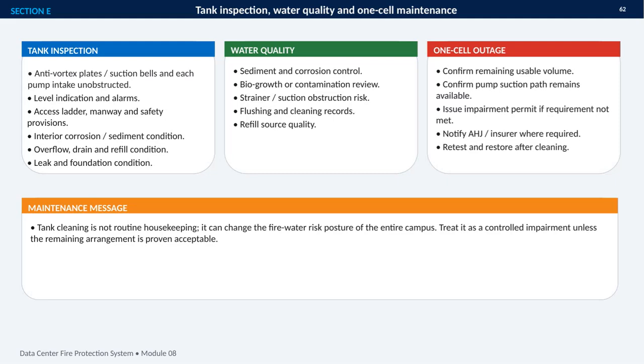This section focuses on tank inspection, water quality, and the controls required when one tank cell is taken out of service. During inspection, I want to verify that anti-vortex plates, suction bells, and every pump intake are unobstructed. We also check level indication and alarms, access and safety provisions, interior corrosion or sediment, overflow, drain and refill functions, and any signs of leakage or foundation damage. Water quality is equally important. Sediment, corrosion, biological growth, and contamination can restrict strainers or pump suction paths.